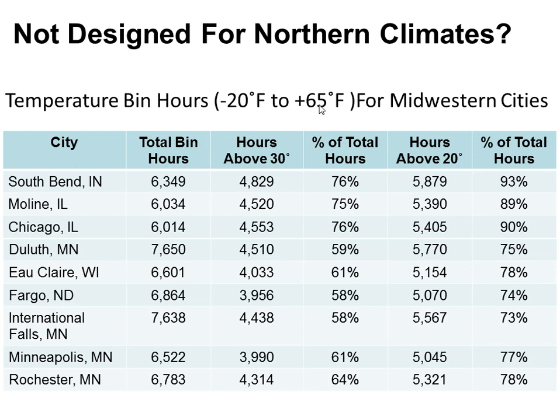So the vast majority of our year, it's below 65 degrees outside, which doesn't feel like it right now, but obviously the rest of the year it's pretty cool. We often think of Chicago winters as being cold, 0-degree weather, which we usually get, although this winter we didn't get that. But the reality is we don't hardly ever get that.